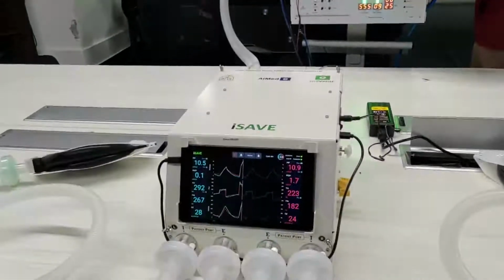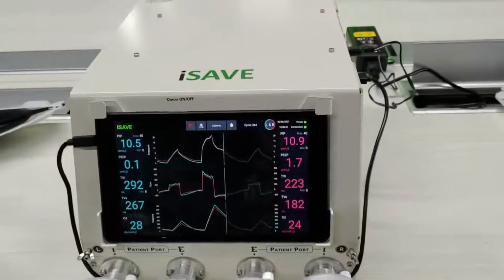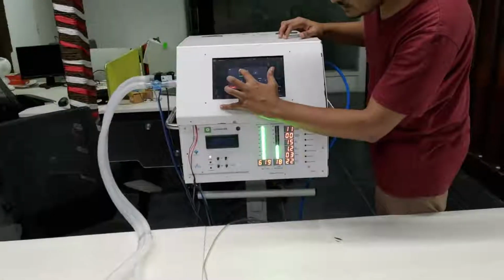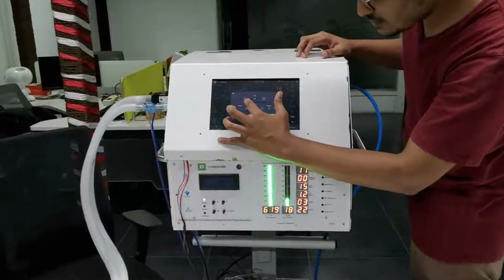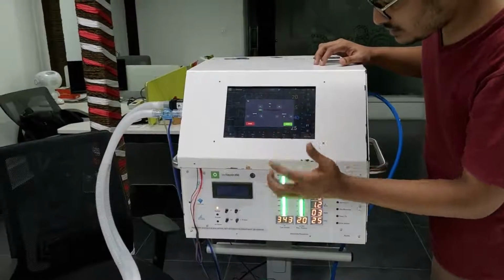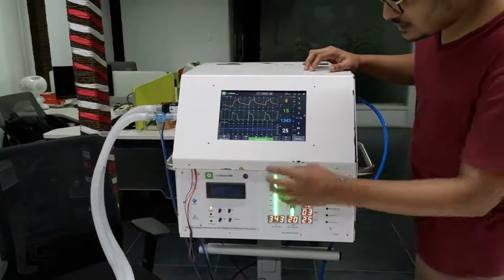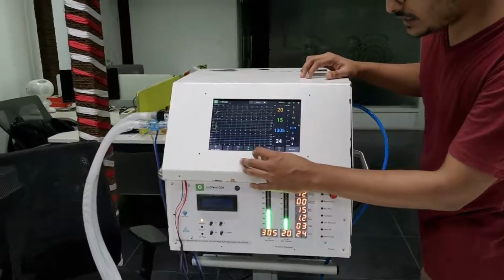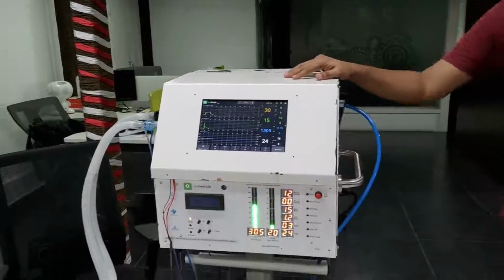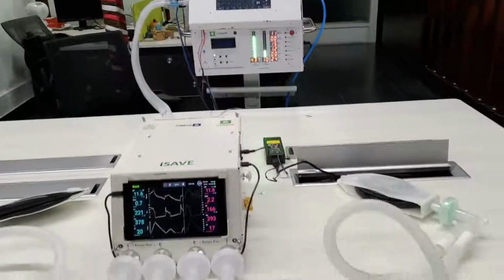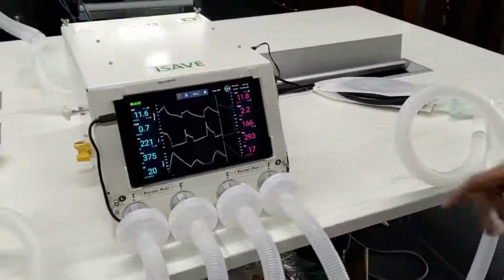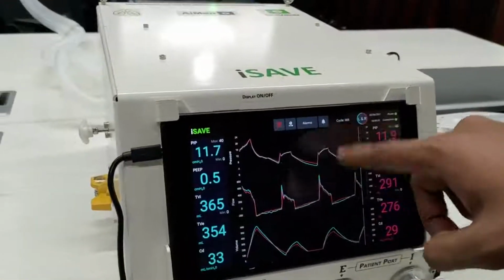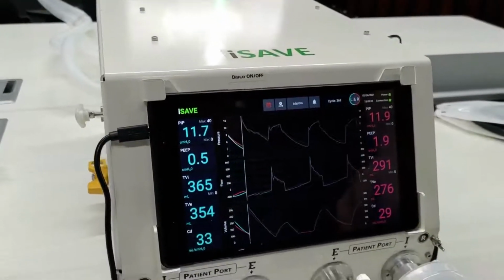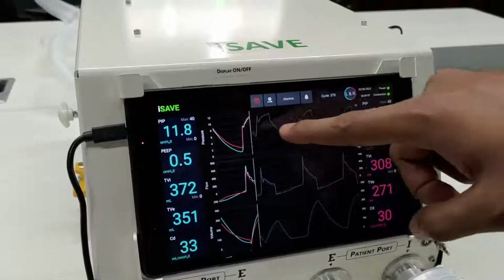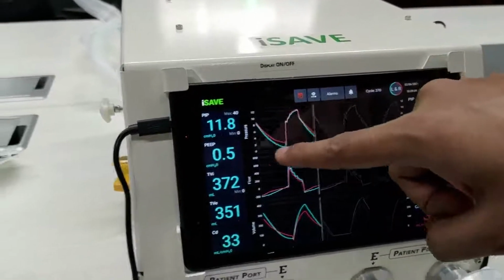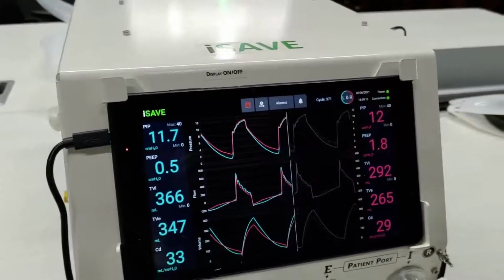So we save our settings. So let's reduce the pressure a bit. Let's put 10 cmH2O as our PIP. Our RR is the same, 15, IE is 1:2. Let's see what's happening on the iSAVE side. So here you can see a very different graph. We got pressure control on both patients. So our P peak is around 10 to 11, around there.